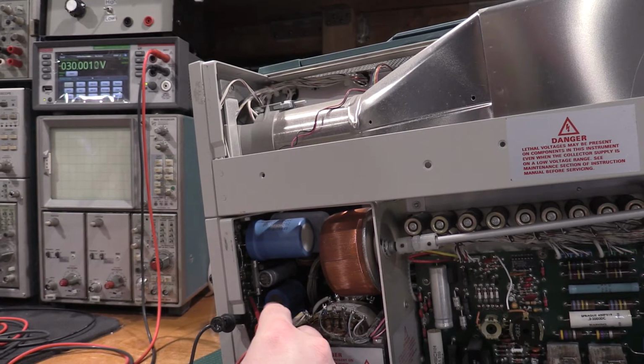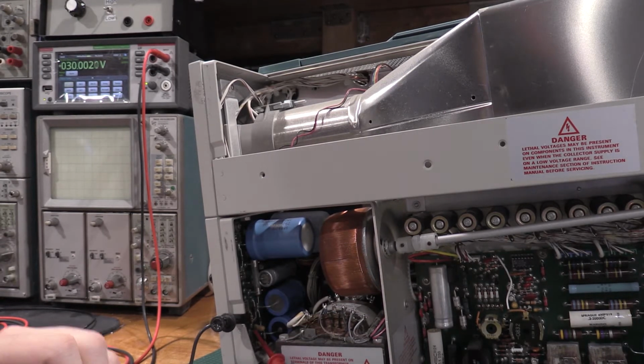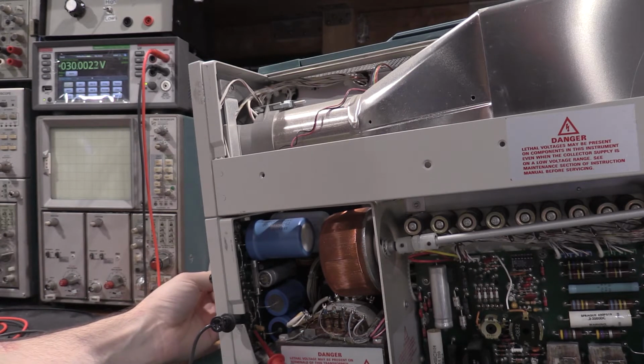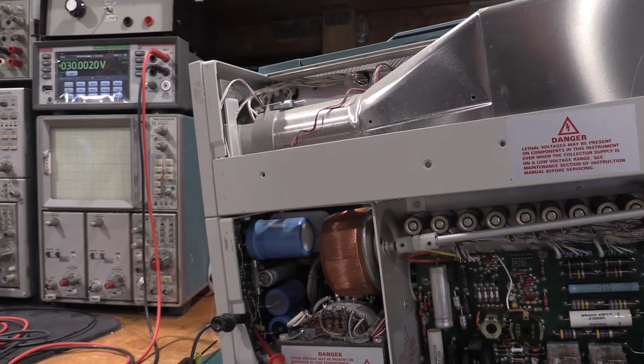And then 30.002. So they are within 0.5% of rated voltage, and they are within 0.5% of each other, which is necessary for the 577s. So I can move on to popping the base off of the 177 and get that calibration started. So I'll get everything rearranged, and then I'll be back.